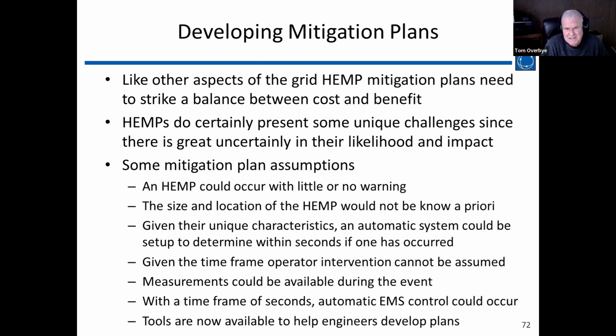An automatic system, a key part of the mitigation, is to know whether an HEMP has occurred. The good thing about a HEMP from a detection point of view is that it has a pretty unique signature—you're going to get a lot of harmonics in your transformers very quickly. So I think within seconds you could set up an automated system to determine that a HEMP has occurred.